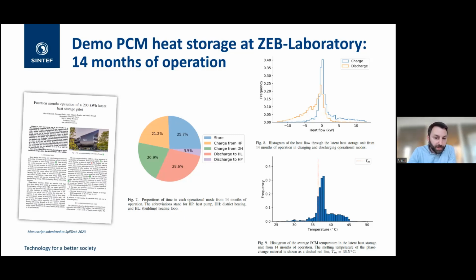You see that this is the biggest part. So we have used it a lot to discharge directly to the heating loop without using the heat pump. In that case, we just run a water pump to circulate the water and nothing else. It's a very cheap way to heat the building, maybe when the electricity price is very high, because you have generated the heat before. And then you have in green the charge from the district heating. So it seems to have been almost equivalent to the charge from the heat pump that is in orange in terms of time of use.